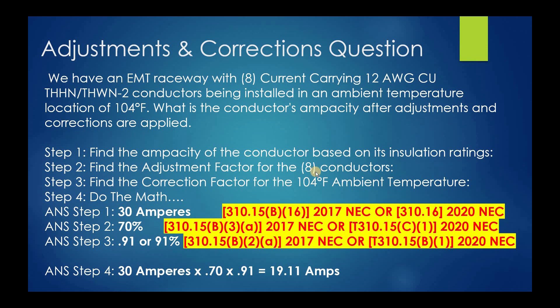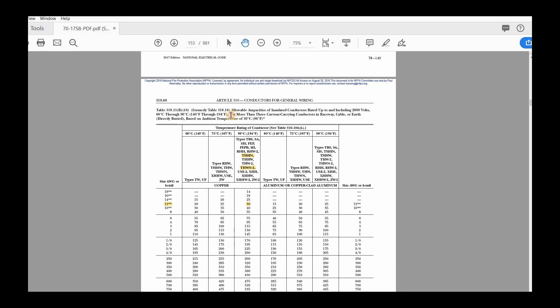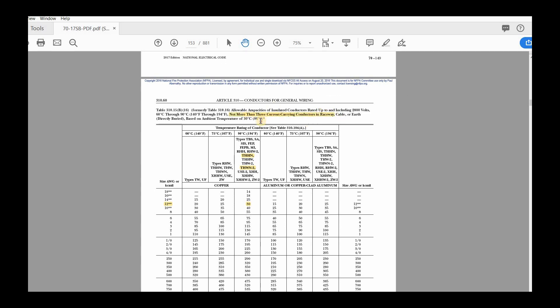Now step two: we have to find the adjustment factor for those eight conductors. Why? Because to use the ampacity in this table, it must be not more than three current-carrying conductors in a raceway, and we've got eight. Also remember, this table is based on 30 degrees C, which equals 86 degrees Fahrenheit. Ours is 104 degrees Fahrenheit, so we realize we're going to have to do some adjustment and some correction to this ampacity value.